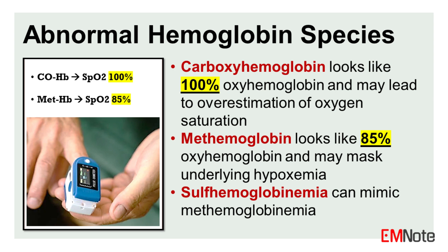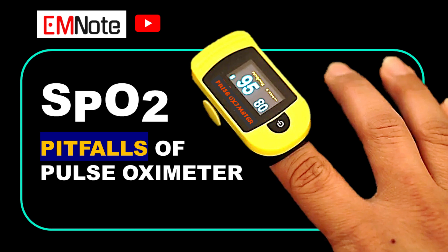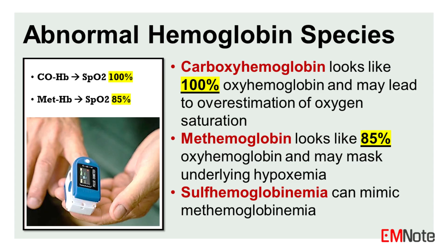The fundamental principle behind pulse oximetry involves the different absorption spectra of oxyhemoglobin and deoxyhemoglobin for red and infrared light. The ratio of these absorption values is used to calculate the oxygen saturation, SpO2. This calculation assumes that only two species of hemoglobin are present — oxyhemoglobin and deoxyhemoglobin. However, in certain clinical situations, other hemoglobin species may be present, leading to inaccurate SpO2 readings.